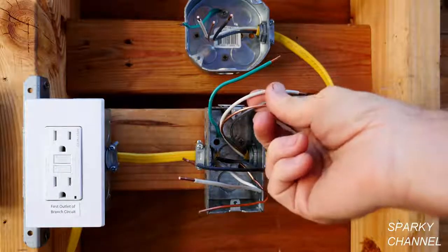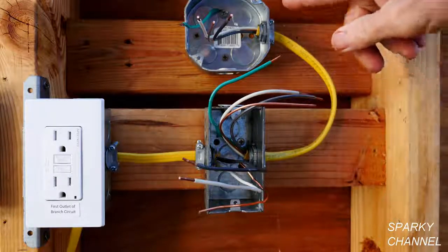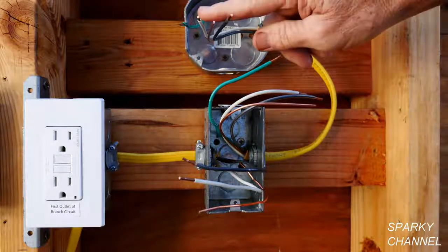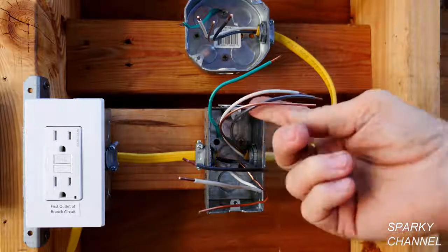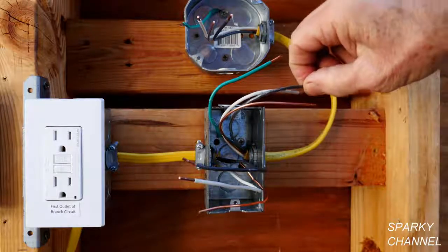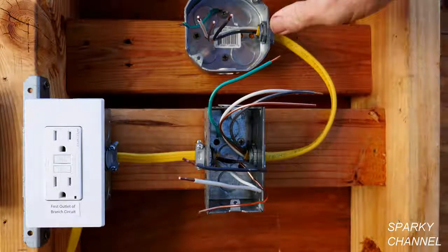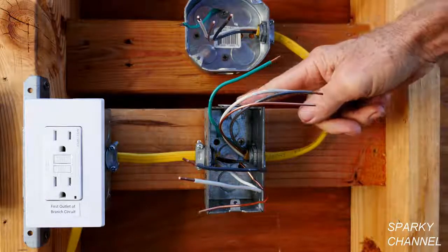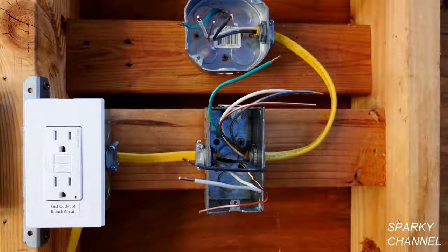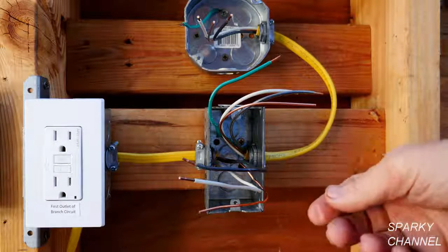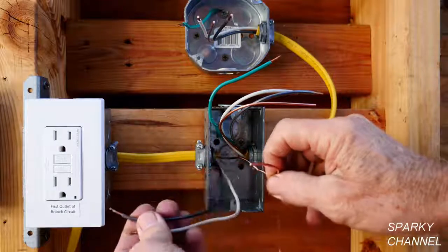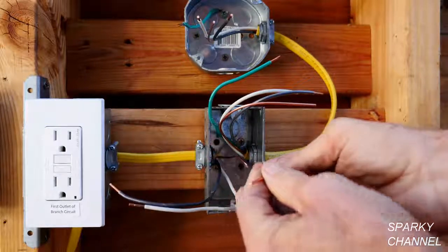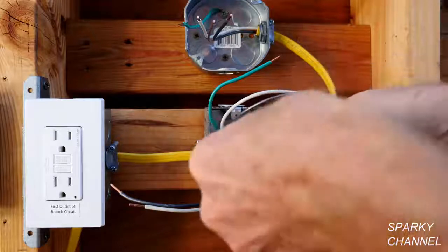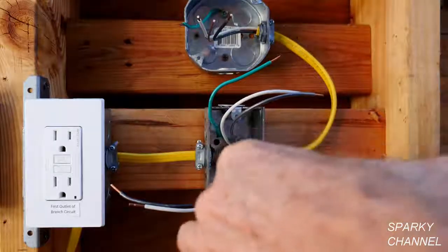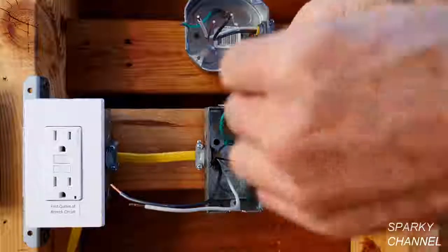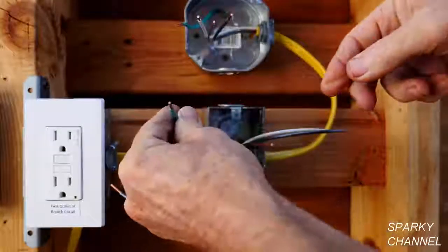Since this cable right here is the one that is continuous by our test with the light box, this is called the load cable, and this specifically is called the load wire. So, and this light will be the load of this switch. So the first thing we're going to do is get all our grounds together. We have a ground that comes from the cable that's bringing electrical energy into the box. We have a ground that is going to the light box, and this ground here is a grounding pigtail.